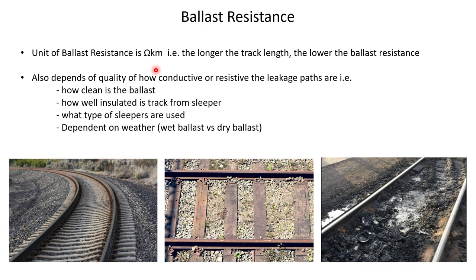There are many factors that determine how good or poor the ballast resistance is. How clean is the ballast — more contaminants mean more leakage paths. How well is the track insulated from the sleeper — without proper insulation the sleeper becomes a leakage path. The type of sleepers used also matters, as does the weather — whether it's a wet or dry weather area.